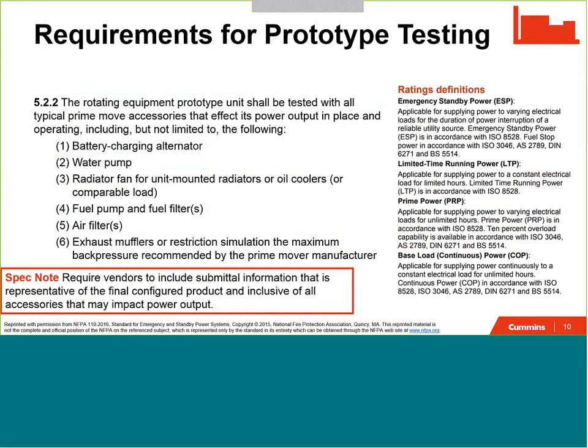So before I go too much further into prototype testing, one of the key pieces to note, and this is again out of NFPA 110, section 5.2.2, is that it specifically requires that for the prototype test, the product shall be tested with all of the parasitic load-inducing accessories, all the accessories that may impact the power of the product. This is important because not all manufacturers necessarily adhere to this, and in some cases that's okay, but in many cases it's not, and it's something at the very least you need to be aware of.